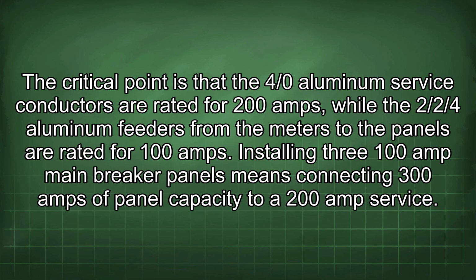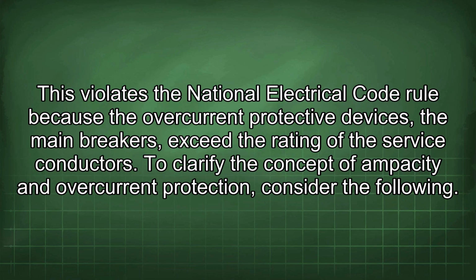The critical point is that the 4/0 aluminum service conductors are rated for 200 amps, while the 2/2/4 aluminum feeders from the meters to the panels are rated for 100 amps. Installing 3 100 amp main breaker panels means connecting 300 amps of panel capacity to a 200 amp service. This violates the National Electrical Code rule because the overcurrent protective devices, the main breakers, exceed the rating of the service conductors. To clarify the concept of ampacity and overcurrent protection, consider the following.